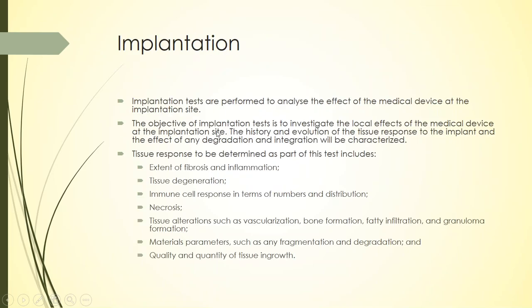So the next one is implantation tests, which is mainly for implanted devices. These are performed to analyze the effect of the medical device at the implantation site, right? So the objective of such a test is to investigate the local effects of the medical device at the implantation site. Tissue response to the implant and the effect of any degradation or integration should be characterized based on these tests.